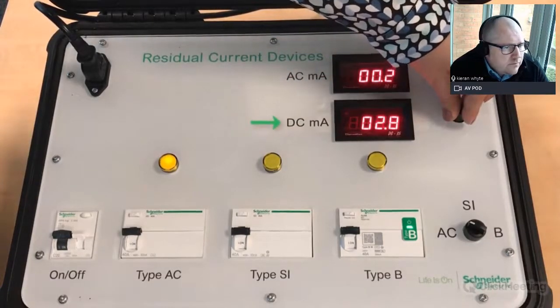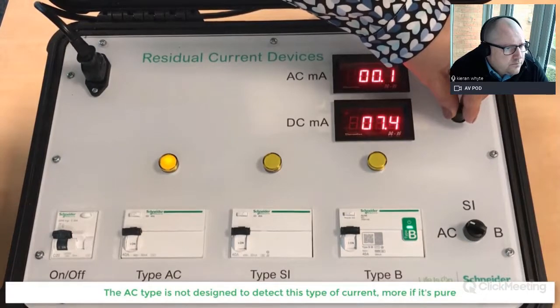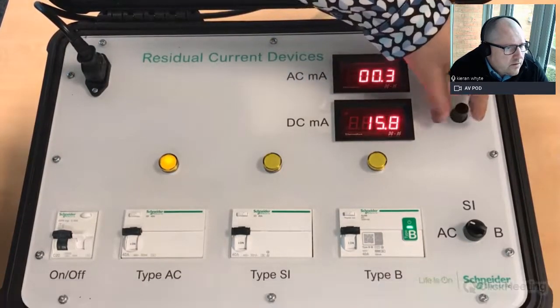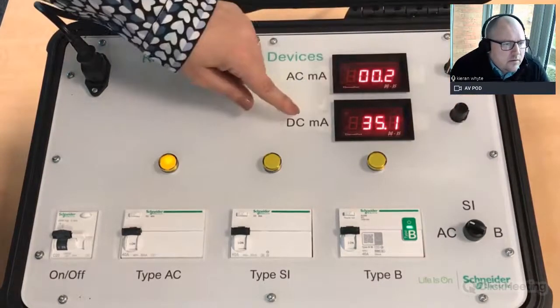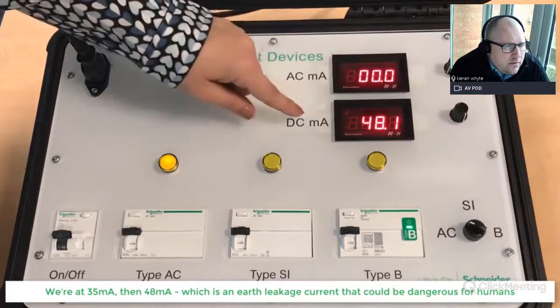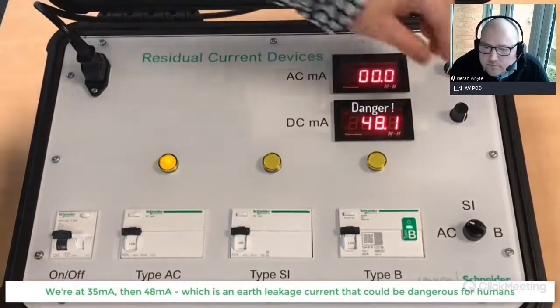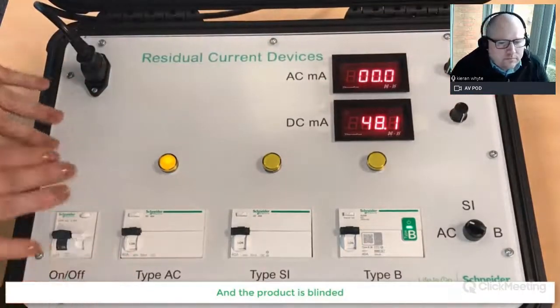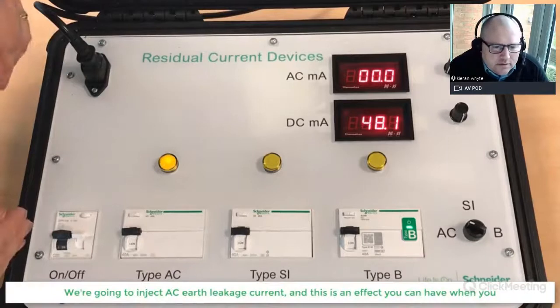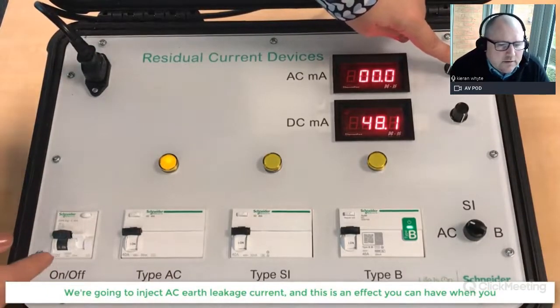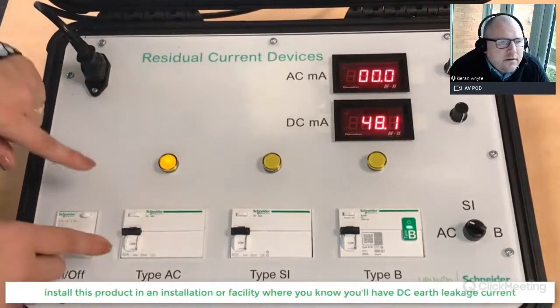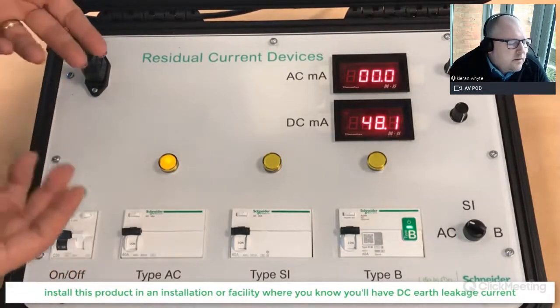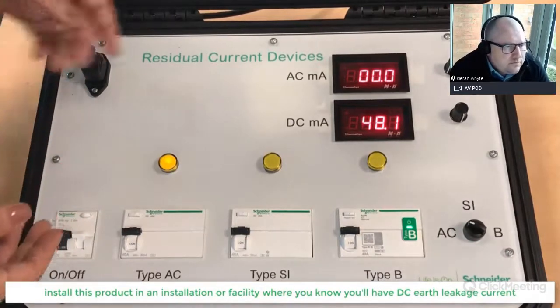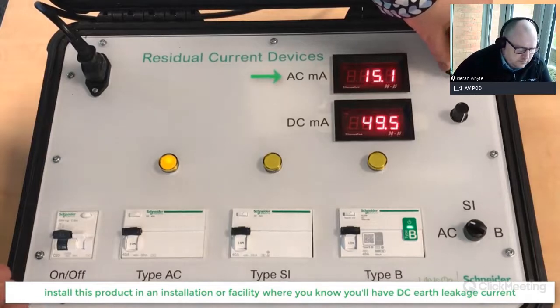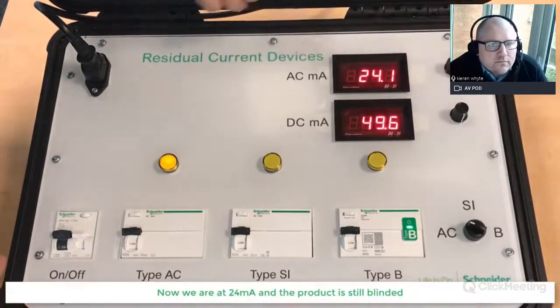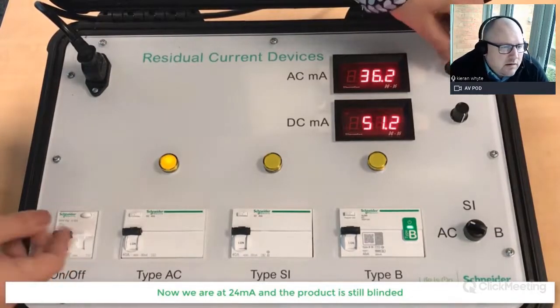As I said before, the AC is not designed to detect this type of current, more if it's pure. So what we're going to see is that we're at 35, 48, which is an earth leakage current that could be dangerous for humans, and the product is blinded. What we're going to see now is that we're going to inject AC earth leakage current, and this is the effect that we can have when you install this product in an installation or in a facility where you know that you will have DC earth leakage current. Normally, before it trips, now we are at 24 and the product is still blind.